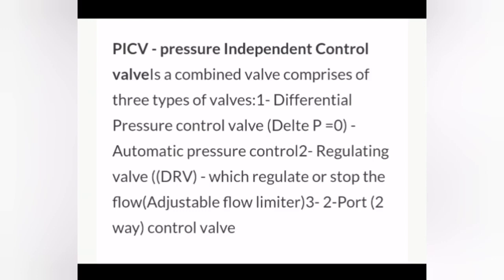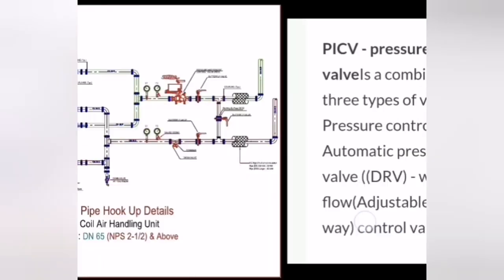It has 3 functions. First one, differential pressure control. Second one is the flow regulation. Third one is the control valve, adjustable flow limiter, or you may call it the actuating valve, which works with the VFD. So I will explain how it works.